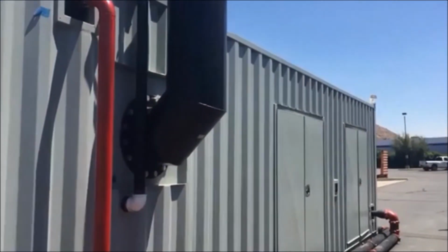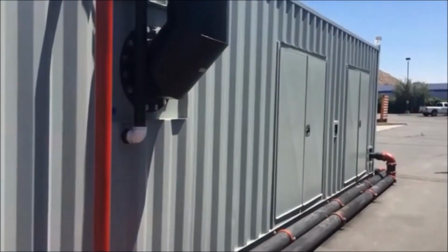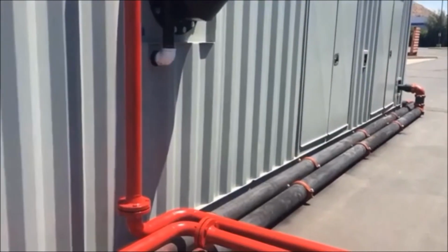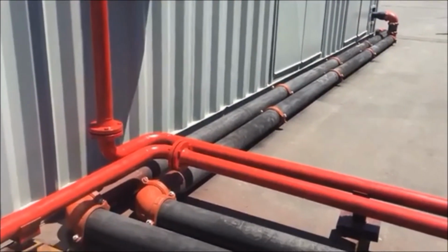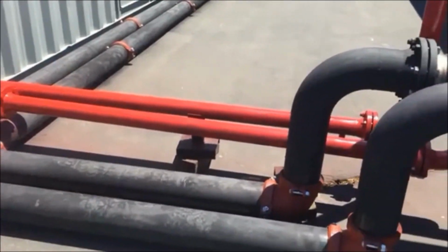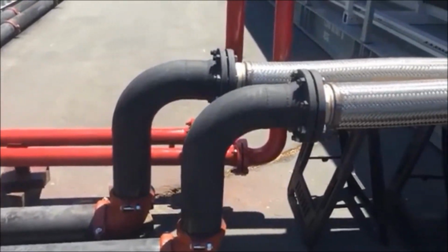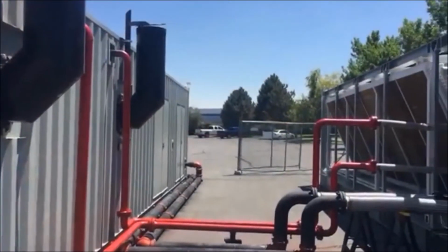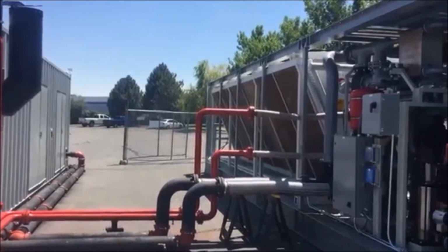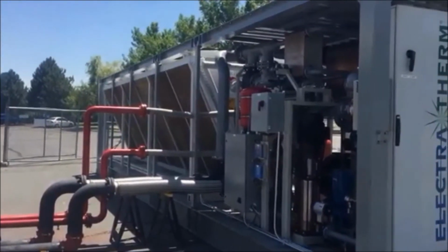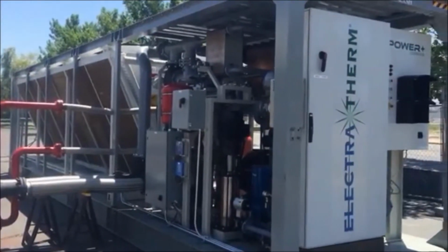The lower temperature jacket water provides the preheat duty of the cycle, and the high temperature exhaust heat provides the evaporation duty. This configuration maximizes the temperature going into the ORC, which helps to drive a large temperature difference between the hot and cold inputs to the cycle, resulting in greater power output.